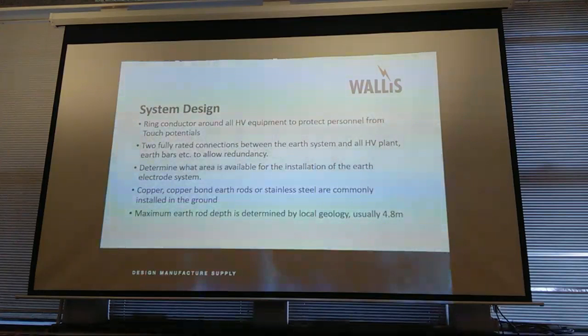Copper bond and stainless steel rods are commonly used in the ground. Copper bond are the big ones. They're the ones you're going to see. Steel with a copper coating. We tend to design mainly for 4.8 metre rods. Now, I tend to use the analogy that if down in London you need to get an earth rod in, and you've got a big bloke with a Kango, you will get an earth rod down to 12 or 15 metres, because it is London clay, and you will just knock them straight in. Whereas in Nottingham, you might be lucky to get half a metre in some places. So again, you need to know what the ground makeup is.